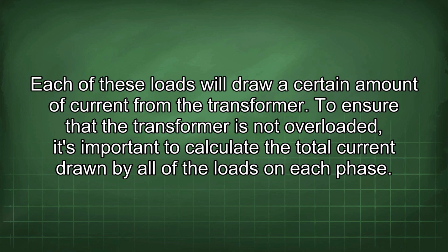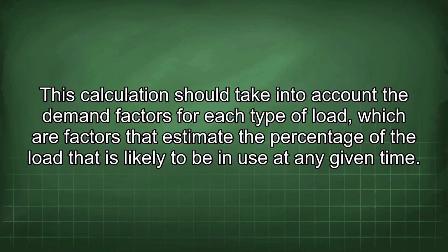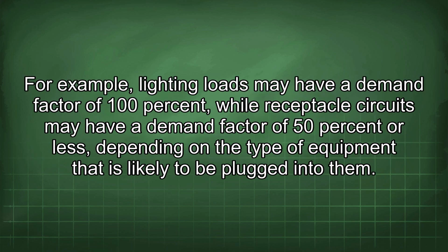To ensure that the transformer is not overloaded, it's important to calculate the total current drawn by all of the loads on each phase. This calculation should take into account the demand factors for each type of load, which are factors that estimate the percentage of the load that is likely to be in use at any given time. For example, lighting loads may have a demand factor of 100%, while receptacle circuits may have a demand factor of 50% or less, depending on the type of equipment that is likely to be plugged into them.